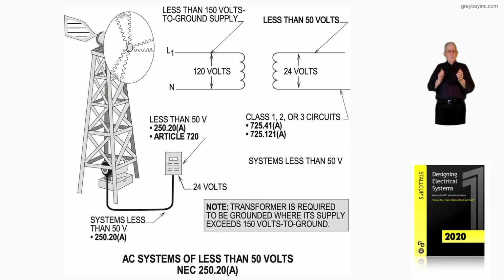And notice you don't ground that secondary. I could even have 240 volts feeding that transformer, because you haven't exceeded 150 volts to ground. See, you could have a 120/208 and feed 208 volt, 240 volt or 120, and you're still in the ballpark. And when you deal with the classification of your circuitry, then we have that listed up there for Class 1, 2, or 3. See 725.41(A) and 725.121(A). And we could see what those Class 1, 2, and 3 circuits are.